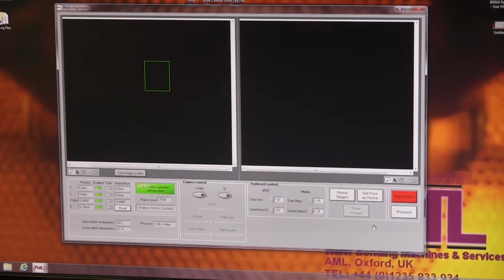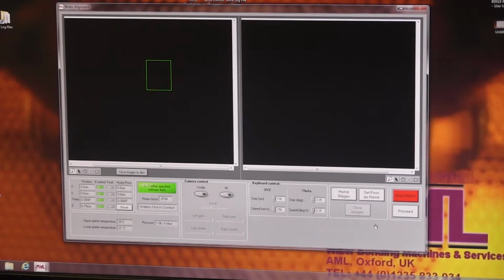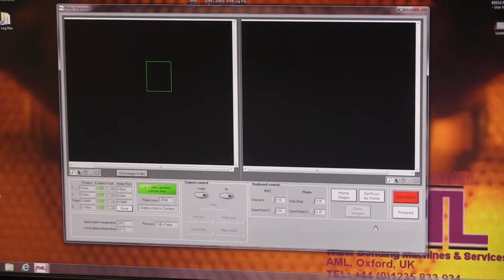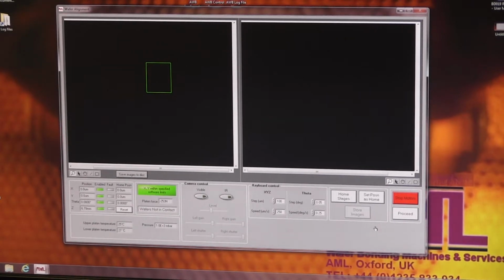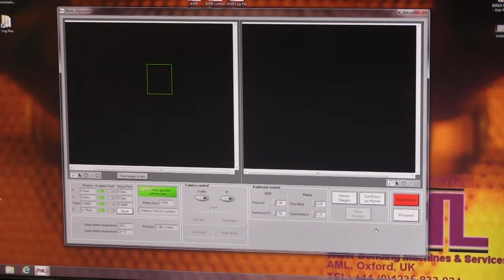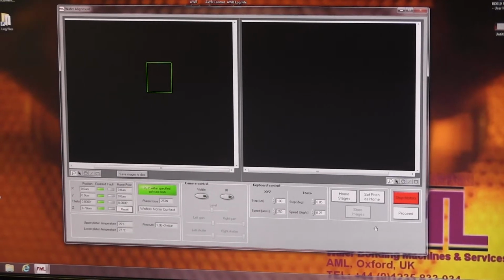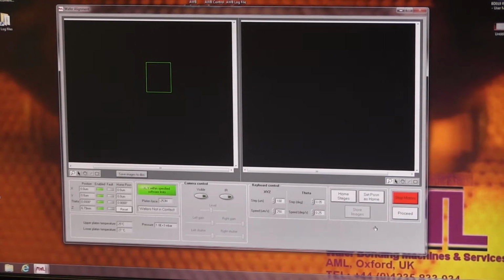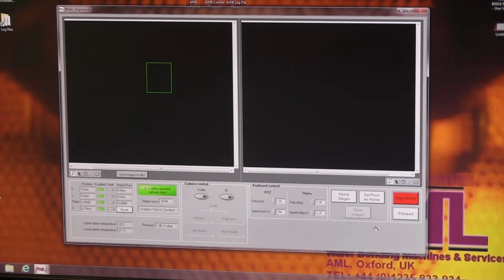Another slight limitation with the system is that in the event of a power loss, it will not remember the position of the motors. So if you've offset the manipulator and then turn the machine off, when you start it up again, it will think that the position it's currently in is the home position — it can't remember that it's been offset. That's why I recommend sending the stages to the home position before shutting down.